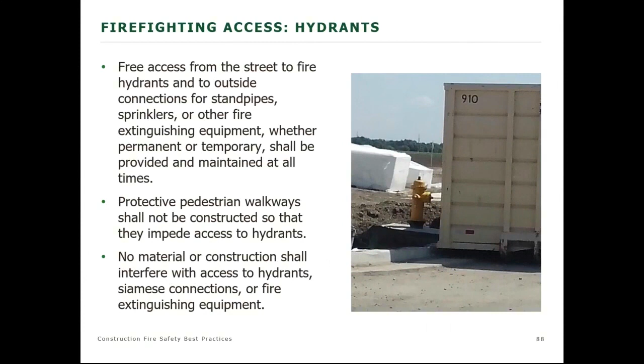Standpipes are probably the most important fire protection system in a building under construction before the sprinkler systems come online. It's the quickest and most effective way to convey water to upper floors. Okay, so the code says once it hits 40 feet, you have to have a standpipe in place that goes up with the building, one floor below the floor of active construction. You have to have an FDC, fire department connection, which is conspicuously marked and readily accessible. And the IFC provides that you need to have a minimum fire flow of 500 gallons per minute. In this picture, you're not supposed to have debris in there at any time, really.